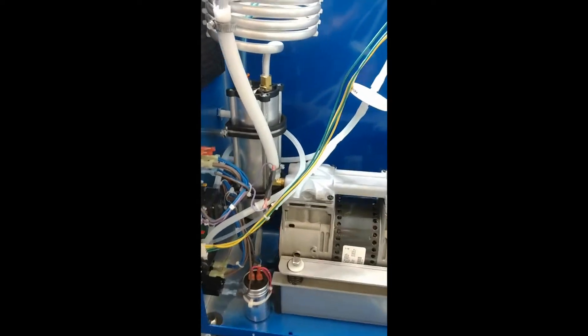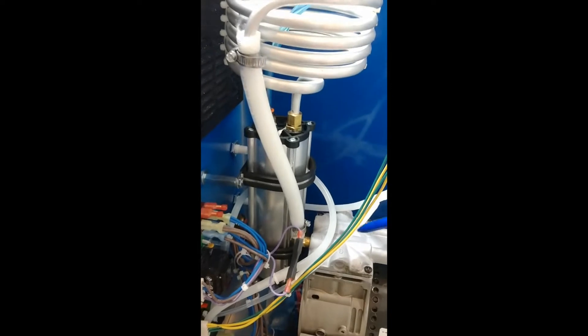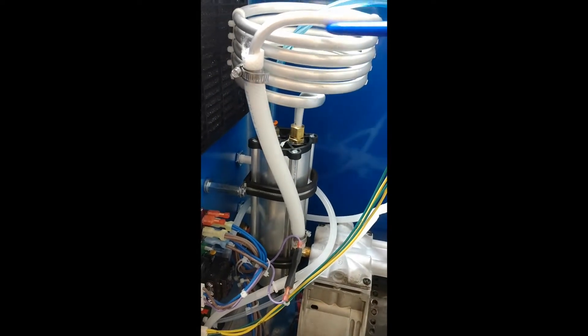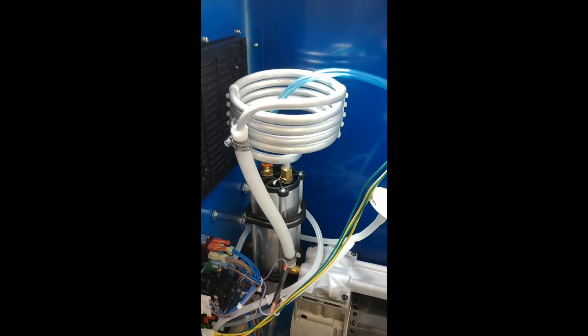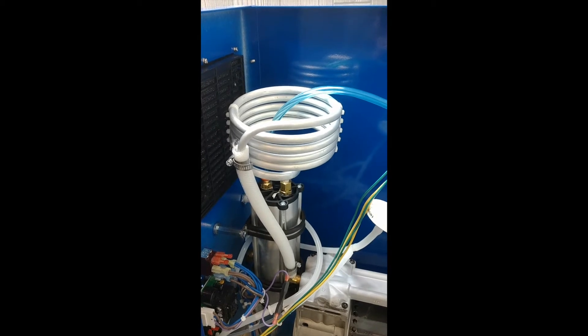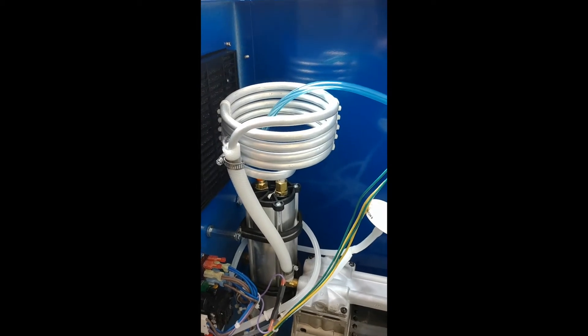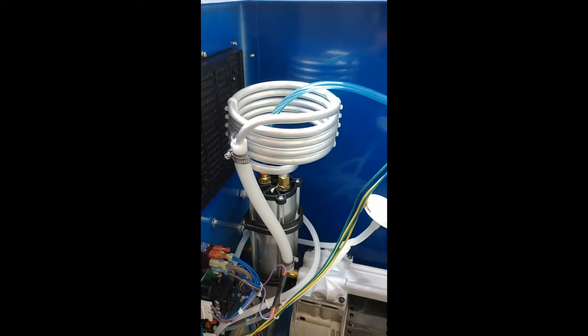This hot compressed air goes up this white hose here into the coil of aluminum tube to cool it down. When you cool that air down, a lot of the moisture that's in the air will condense out of it.